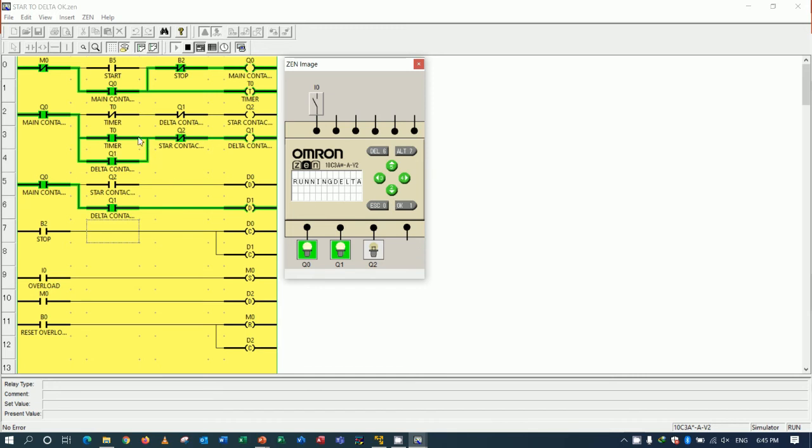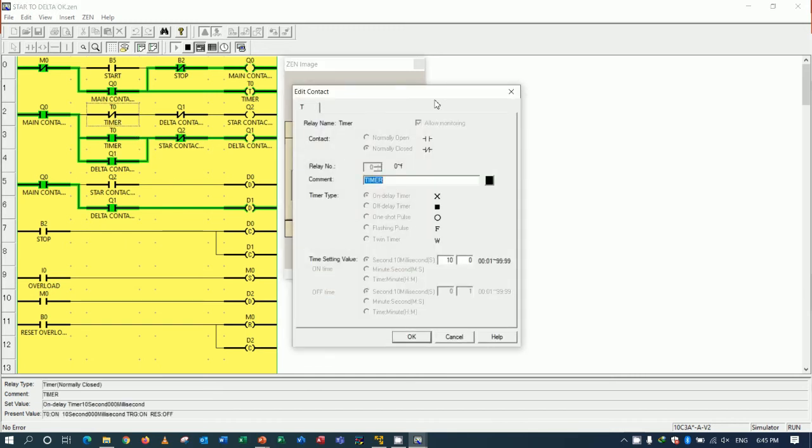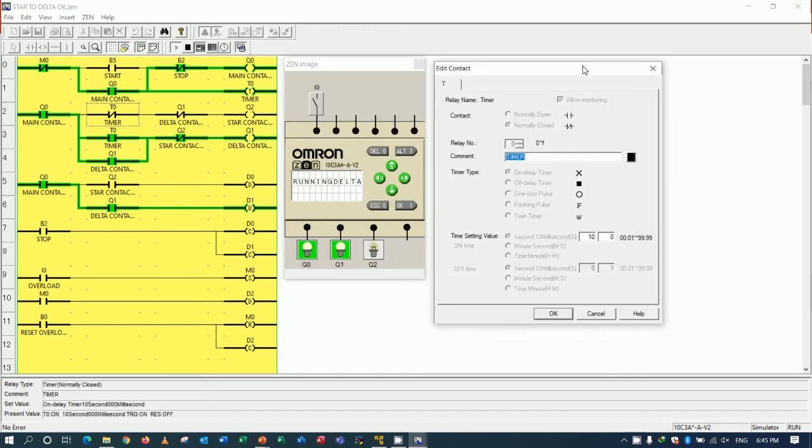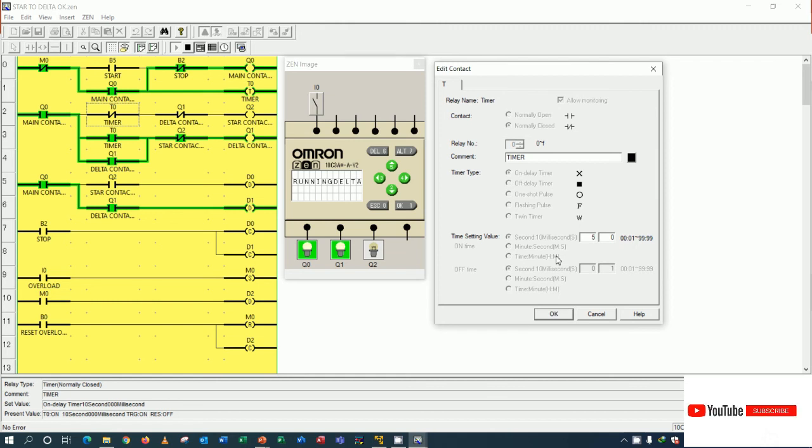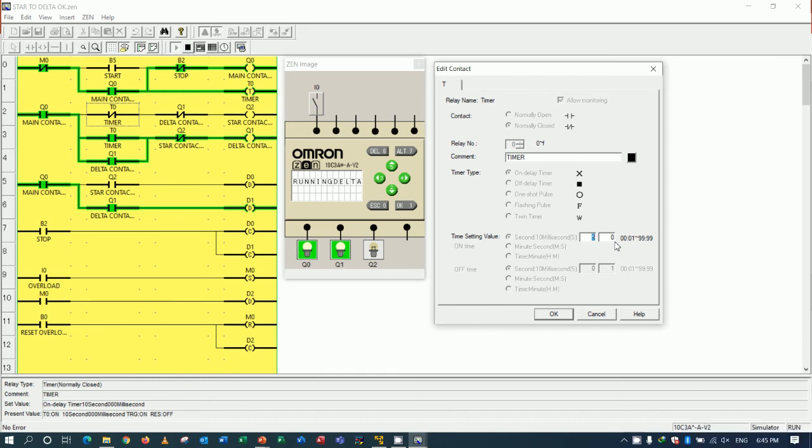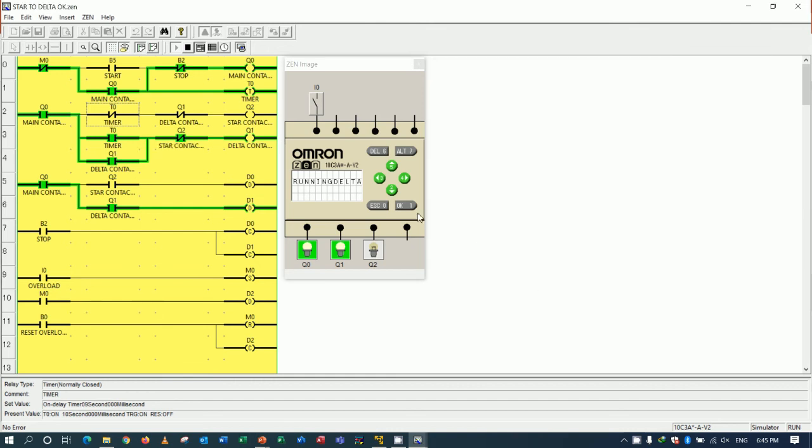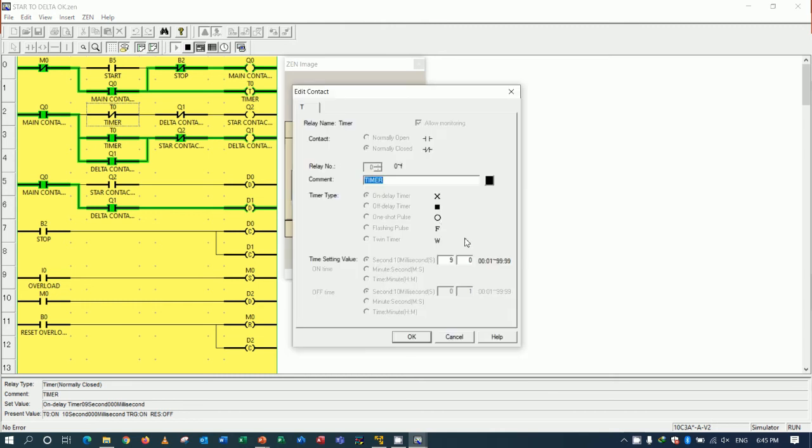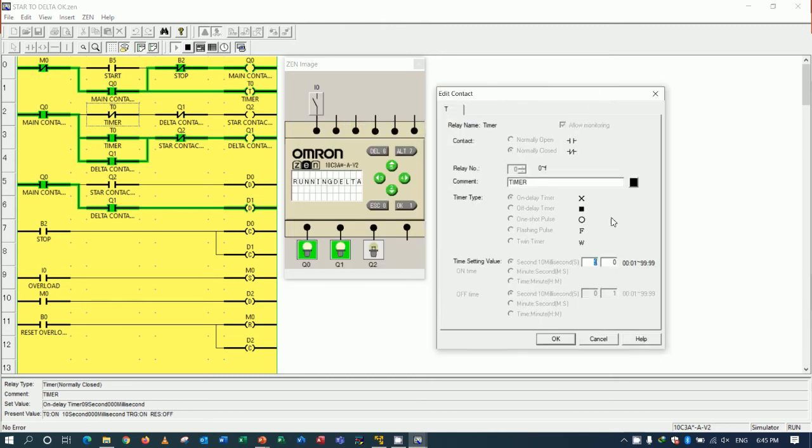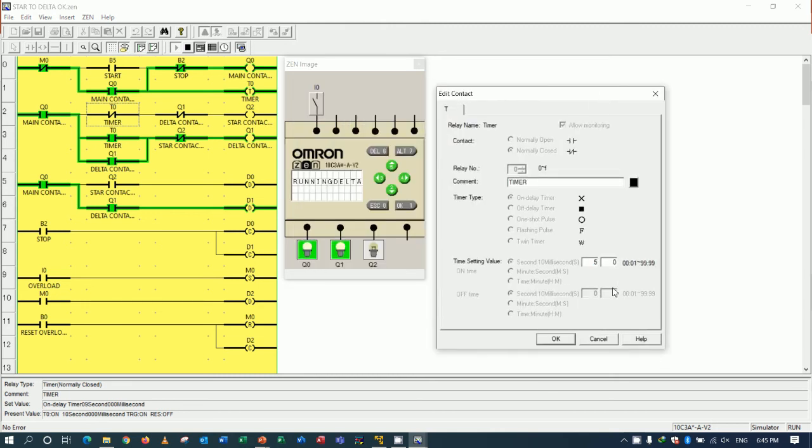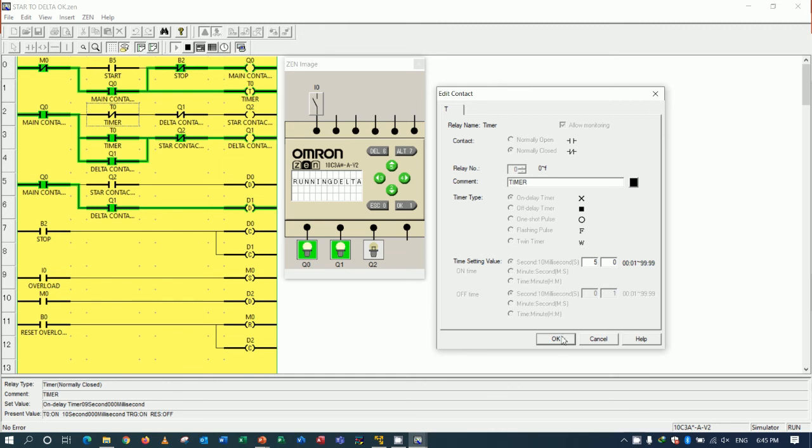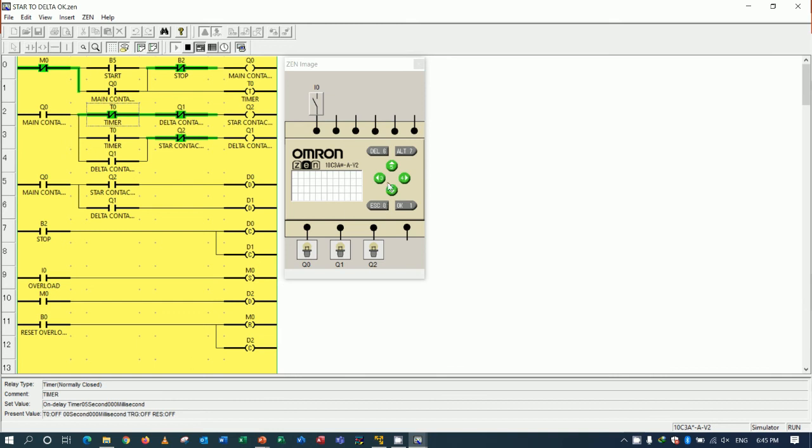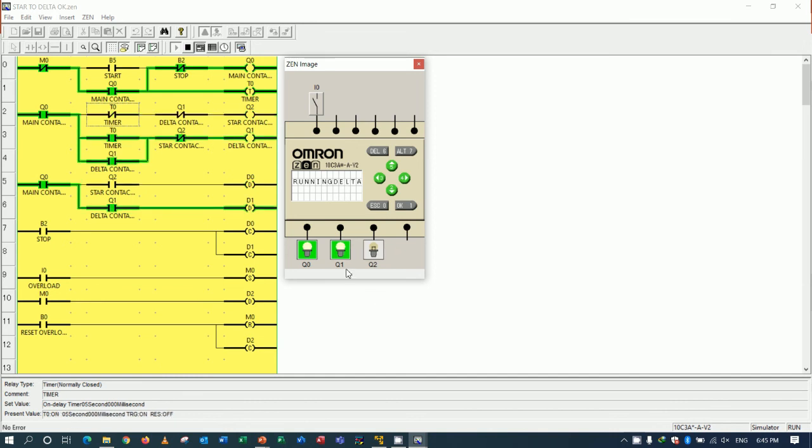And for timer we can change if we write like this. So we can change to example 5 seconds, but actually star to delta maybe 10 seconds or 9 seconds to change from the star connection to delta connection. But example if we would like to change for simulation fast, we can change to 5 seconds. So I will stop first. So if I start again, it will start 2, 3, 4, 5, change to delta connection.